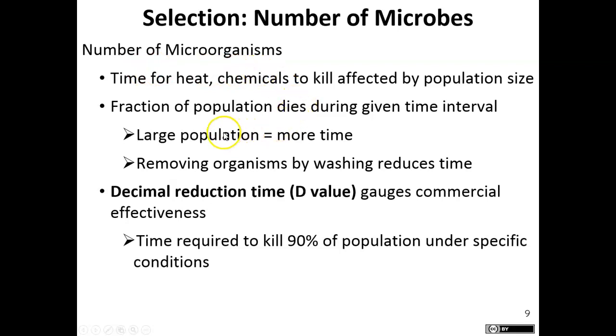The number of microbes. So how many microbes are in the environment that you're trying to kill off? If there's a lot of microbes, it's going to take longer than if it's a small population. When I'm using my autoclave to sterilize media that likely does not have very many microbes in it, because I haven't inoculated anything, I use a 15-minute time period.